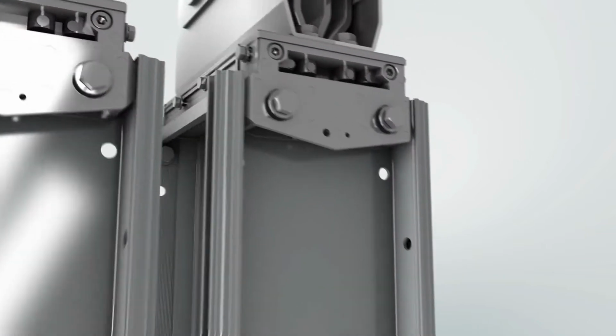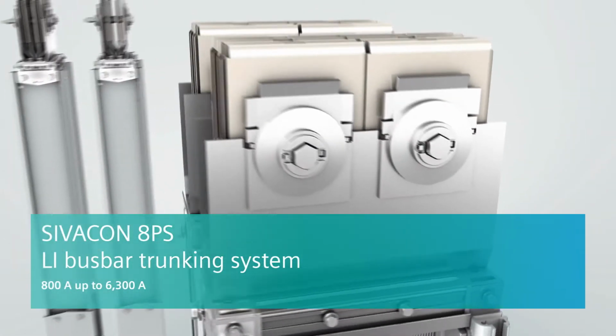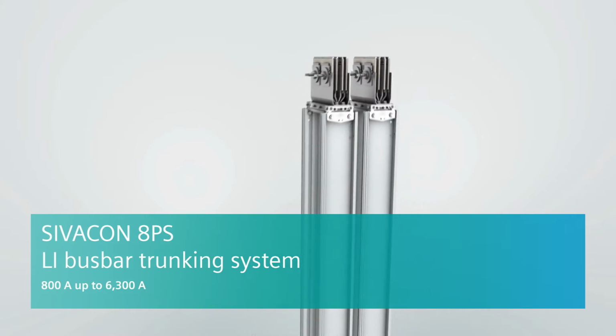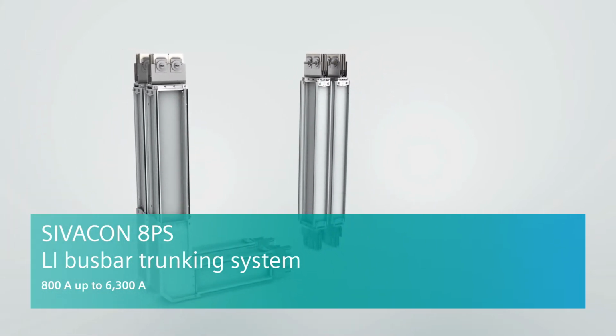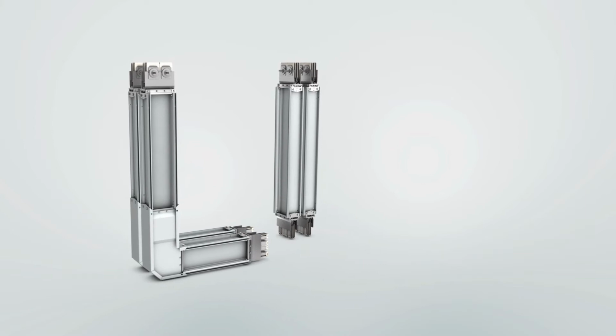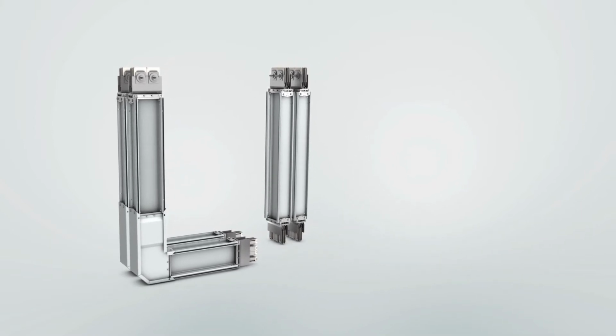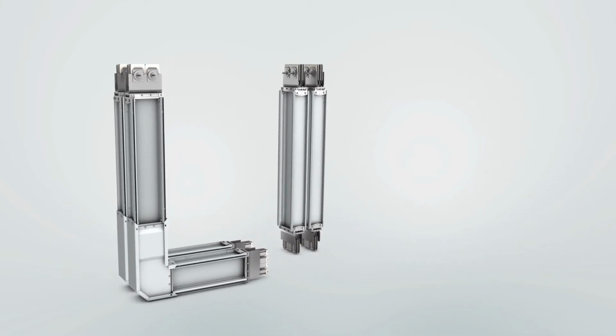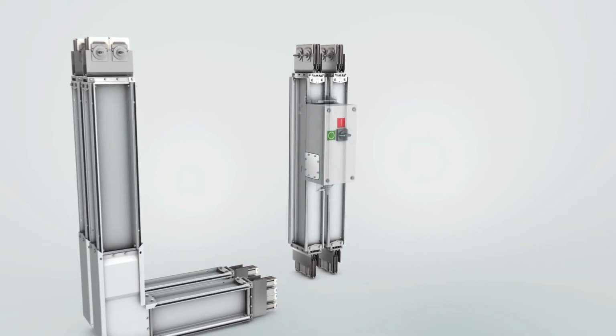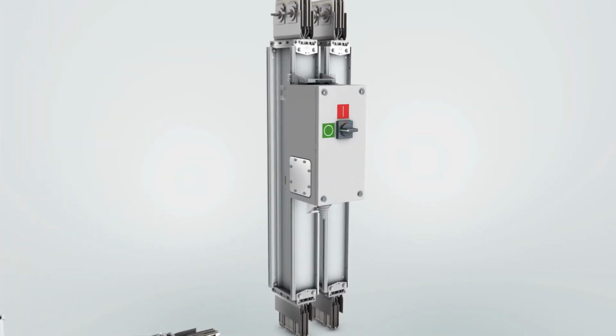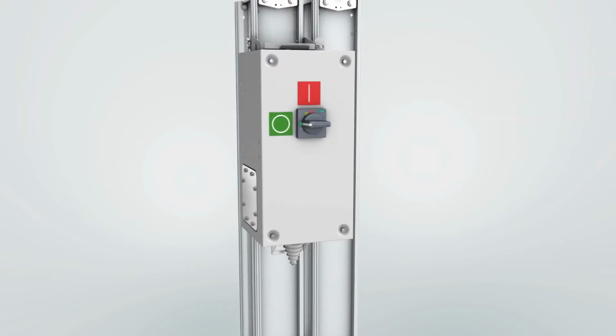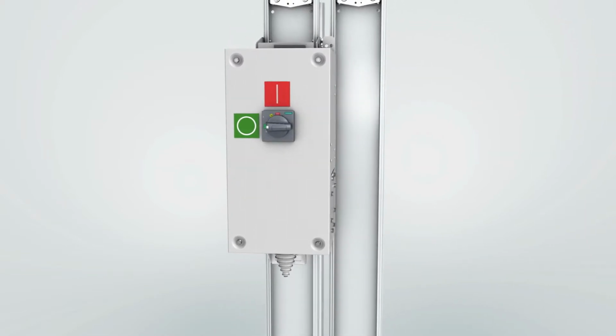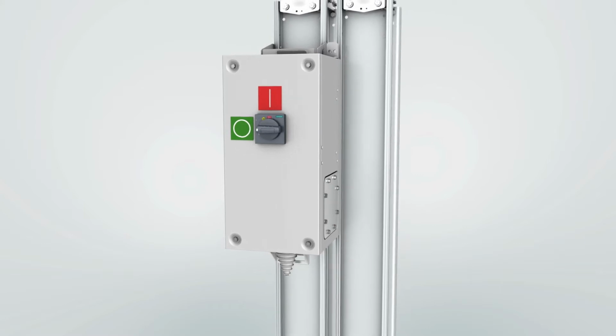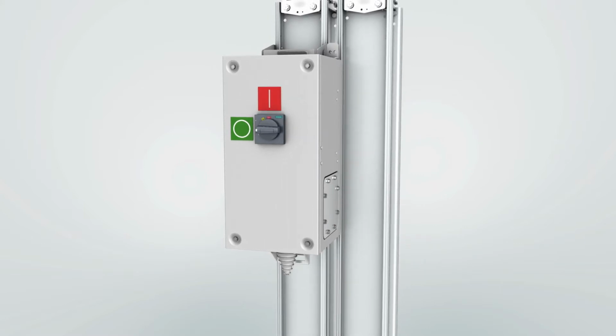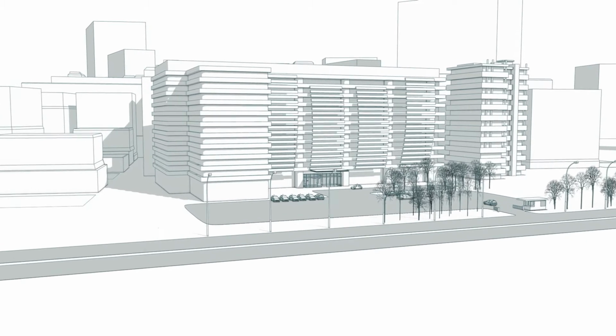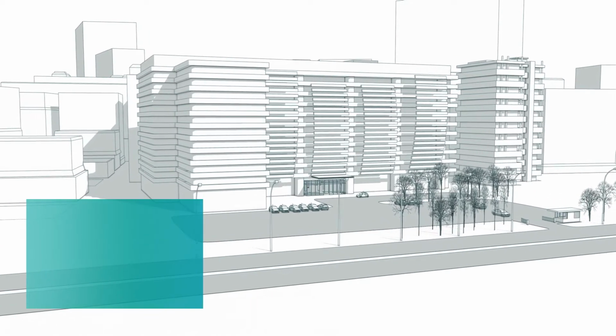The new LI busbar trunking system from the SIVACON 8PS family meets all these requirements, thanks to Siemens' expertise and decades of experience. It allows you to safely transmit large volumes of electricity across long distances, even in very small spaces. The LI system covers a current range from 800 ampere to 6,300 ampere, with tap-off units from 50 ampere to 1,250 ampere, making it suitable for countless applications in infrastructure and industry.